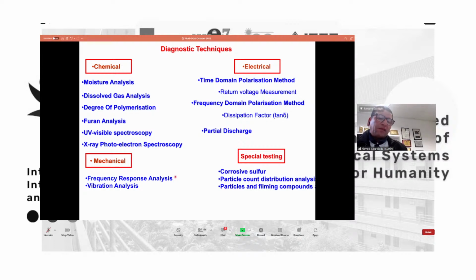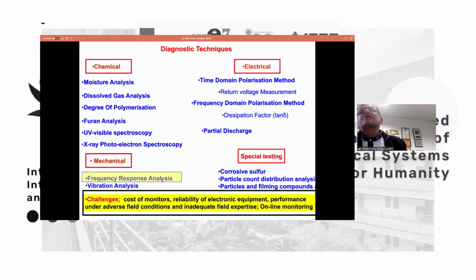For example, frequency response analysis is responsible for detecting any mechanical deformation in the core or in the winding. As you know, we don't have a window to look inside the transformer and see what's happening inside, so frequency response analysis is one of the techniques that can discover the mechanical integrity of the transformer externally.